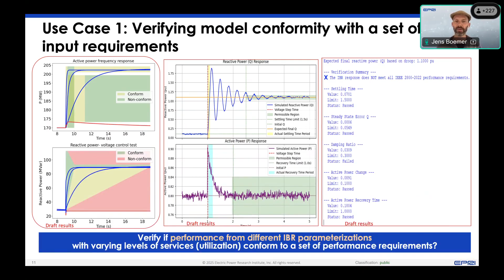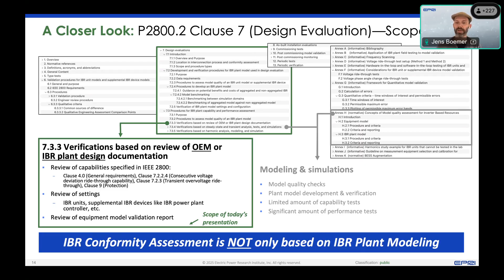But today we're going to look at the OEM and plant design documentation, which is also specified in clause 7.3.3 of 2800.2. In general, that includes a review of capabilities, review of settings, and review of equipment model validation reports. So the key message is that IBR conformity assessment does not only have to be based on IBR plant modeling.